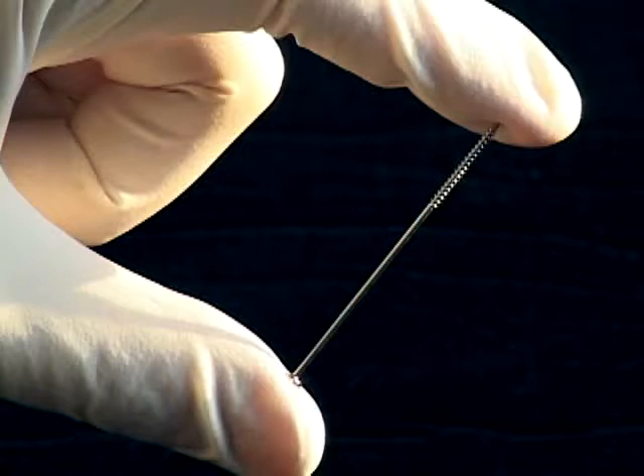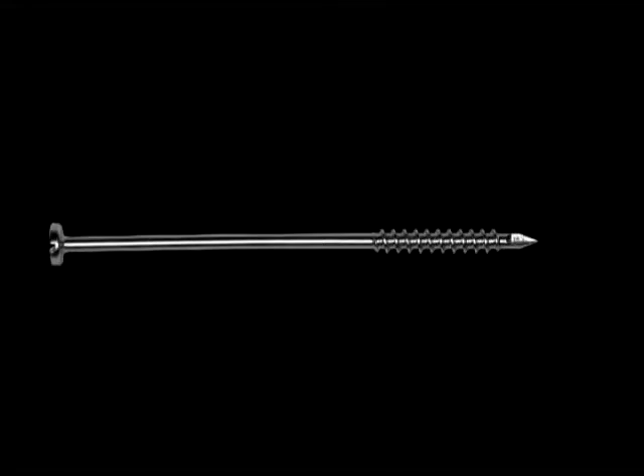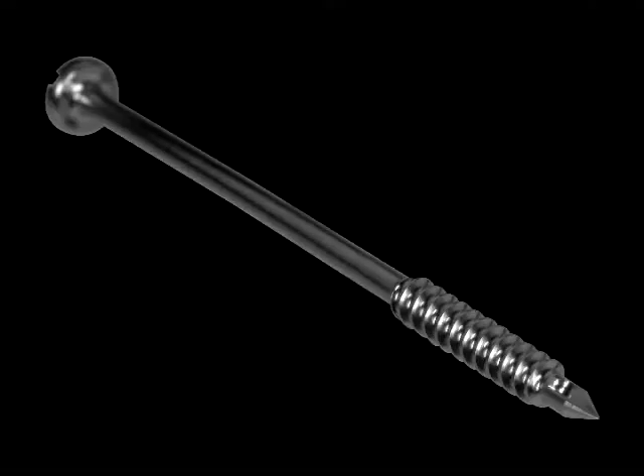In addition, the head of the screw is cruciform with a central locking hole to reduce blade travel and assist in screw stabilization. The proximal shaft is not threaded, acting as a lag screw with an outer diameter of 0.045 inch, while the distal outer thread diameter is 0.062 inch. There is a 3 mm guide extension tip which cuts through the medullary canal and allows the screw to follow along a pre-drilled glide path.